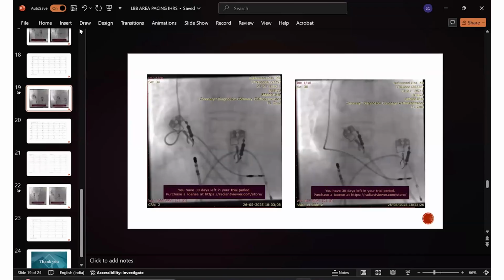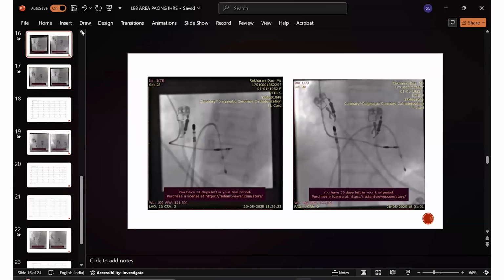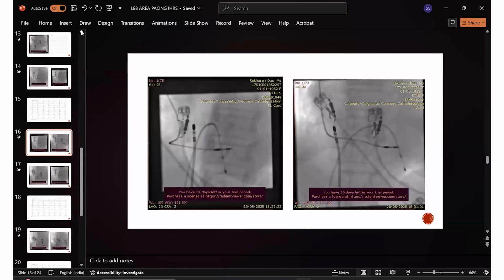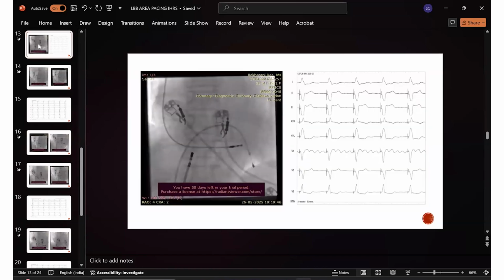And another point I wanted to add. So when we did the lead biomechanics study, because the septa were very thick, we used to give excessive torque just to see how resistant the leads were, and almost all the leads had insulation break and insulation damage. It was most noted with the Abbott Tendril lead as well as the Boston leads. Surprisingly, the insulation with the 3830 was very good, in spite of the torque rising within the lead to be the highest. We didn't see that degree of insulation damage with the 3830.